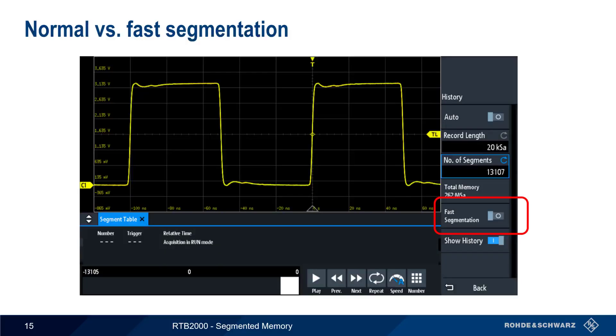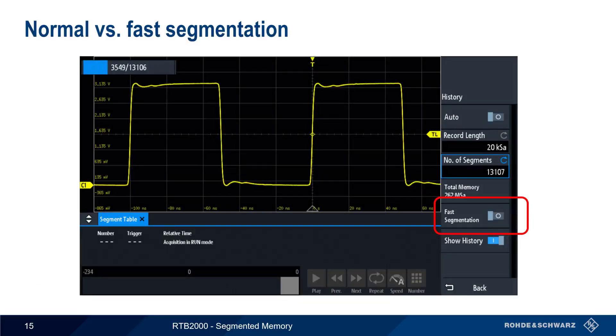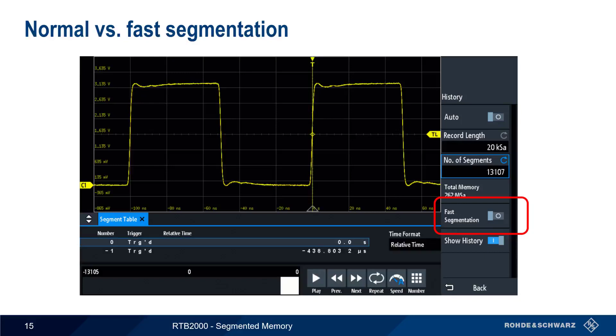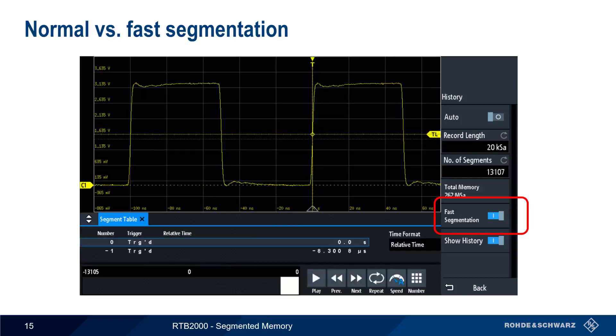Let's compare these two modes. With Fast Segmentation off, the RTB processes and displays the waveforms as they're acquired, which increases both blind times and the total time needed to fill the history. If Fast Segmentation is turned on, the waveforms are stored in history without processing or updating the display — the acquisitions occur much more quickly and blind times are substantially reduced.